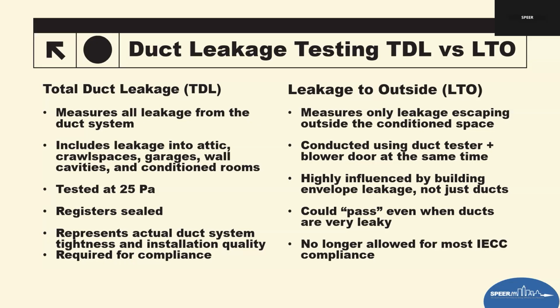For example, in a very tight home, the blower door can artificially mask duct leakage, letting a poor duct system pass. On the other hand, a leaky house can make a good system look worse than it really is. Because of those inconsistencies, LTO made enforcement very difficult. Results varied from house to house, even when they had the identical duct system. For those reasons alone, LTO is no longer allowed in most IECC compliance pathways.